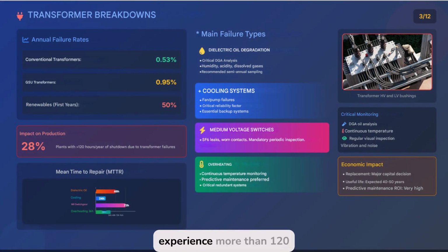28% of plants experience more than 120 hours of downtime per year due to transformer failures. This downtime not only impacts operations, but also translates into real economic losses, especially in facilities subject to PPA contracts, where every hour of downtime means lower revenue. Average repair time is also key. Dielectric oil failures can take 48 hours to resolve, cooling failures around 24 hours, and problems in medium voltage switchgear up to 72 hours. Even overheating results in at least 36 hours of downtime. These cumulative times seriously compromise profitability.